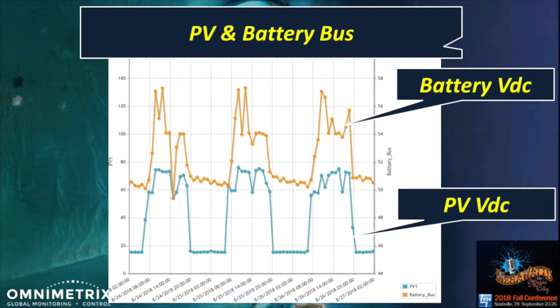So what we see is that the photovoltaic, P1, is the blue graph, peaking in the daytime in the middle 70s of volts. Then the battery charger applies that to the battery, which scaled on this side runs in the middle to upper 50s at peak. But here's the real key: when the sun goes down, what does that primary battery energy storage look like? How deep is the dip? Is it making it through the night? In round numbers, with a 48 volt lead acid system, when you get down to 48 volts, you've pretty much consumed half the capacity of the battery. So in this case, they're doing great, they're not stressing that system at all. They sized it right, maybe oversized it, but they're not stressing their system at all.